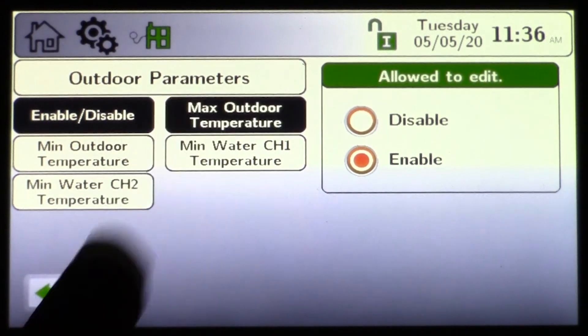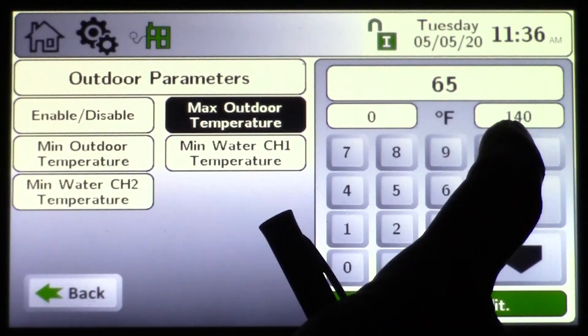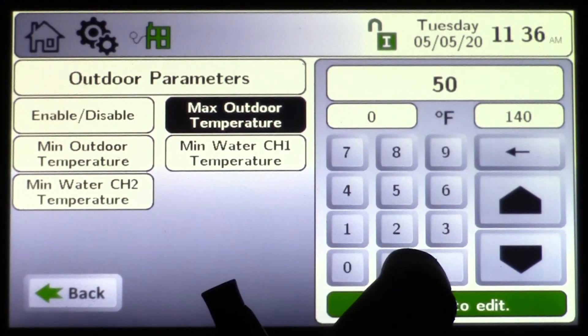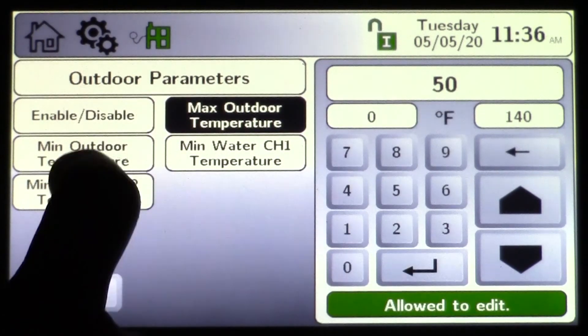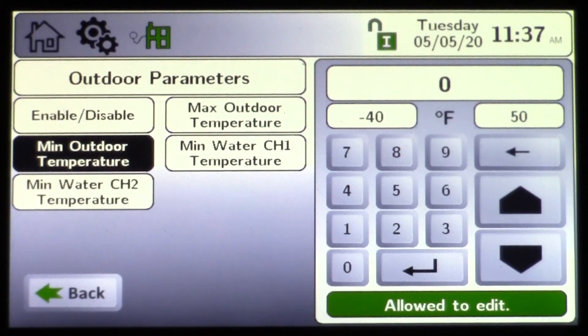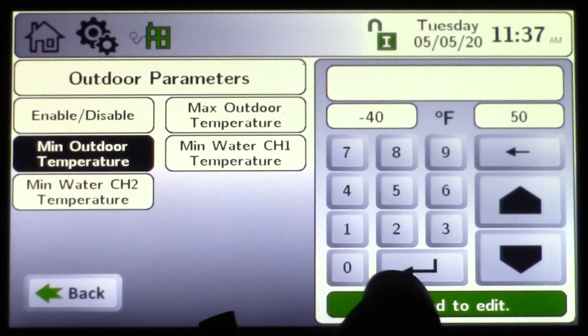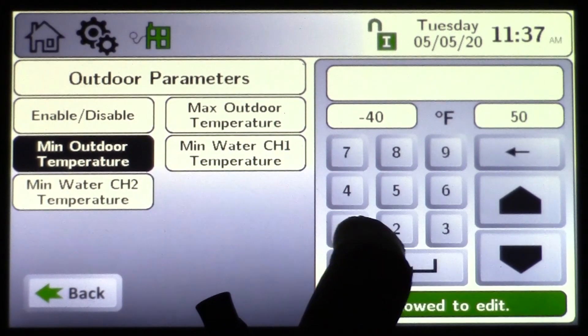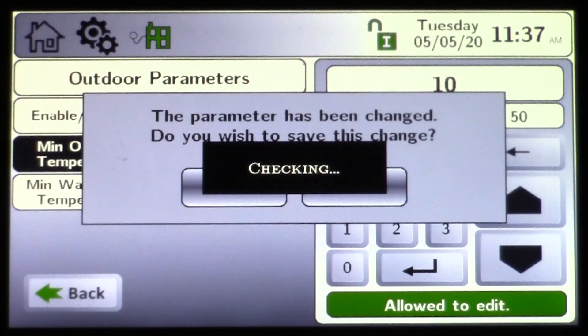Maximum outdoor temperature is where you adjust your max outdoor temp — for example 50 degrees. Keep in mind this is not warm weather shutdown. Minimum outdoor temperature is your design day for your region. If your region is 0 degrees of outdoor air, choose 0. In Des Moines, Iowa at minus 5, you'd type in minus 5. In a region where 10 degrees is the design day, type in 10.